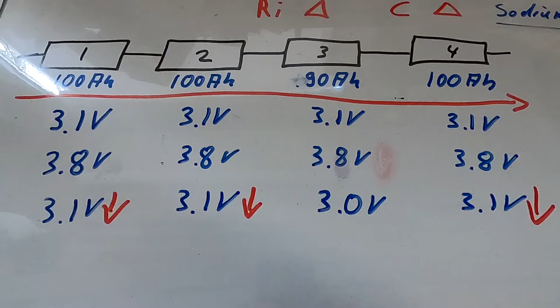So now your balancer would kick in and starts discharging these 3 cells, because this is your lowest, it doesn't touch this one. And if you would further discharge this battery to 2.5 volts per cell now, it will still keep discharging these 3 cells here, because this is your lowest. It's just trying to balance all 4 cells. And this is repeating all the time then. When you charge and discharge, when you cycle, when you use your battery, it constantly balances either your cell number 3, which is your low capacity cell, or it balances the other ones when you discharge because they are too high. The balancer will never stop working.